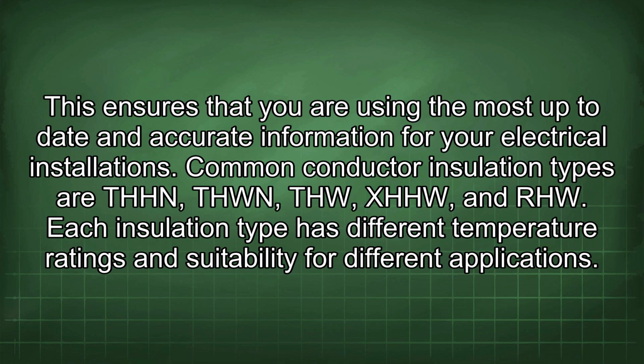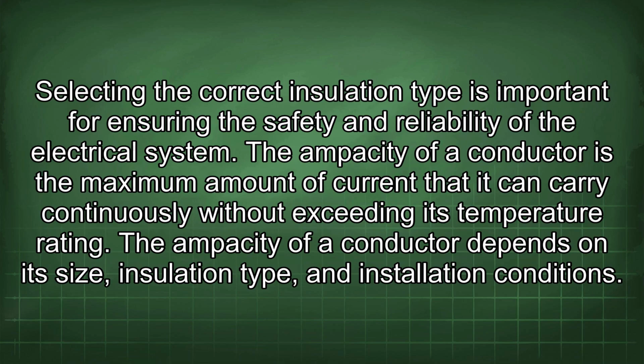Common conductor insulation types are THHN, THWN, THW, XHHW, and RHW. Each insulation type has different temperature ratings and suitability for different applications. Selecting the correct insulation type is important for ensuring the safety and reliability of the electrical system. The ampacity of a conductor is the maximum amount of current that it can carry continuously without exceeding its temperature rating. The ampacity of a conductor depends on its size, insulation type, and installation conditions.